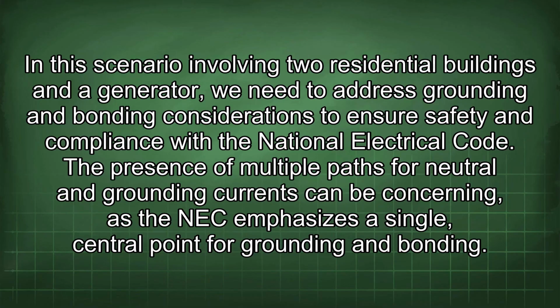In this scenario involving two residential buildings and the generator, we need to address grounding and bonding considerations to ensure safety and compliance with the National Electrical Code. The presence of multiple paths for neutral and grounding currents can be concerning, as the NEC emphasizes a single, central point for grounding and bonding.